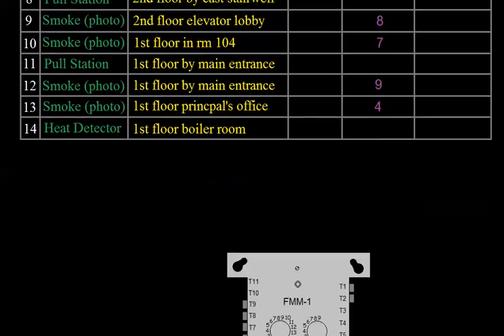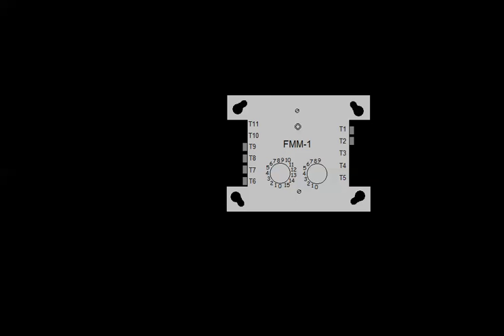The next thing we're going to cover is monitor modules. We've talked about pull stations, smoke detectors, and heat detectors — all addressable devices the panel can communicate with directly. But there are still several devices that aren't addressable: sprinkler devices, conventional heat detectors, conventional duct detectors, and kitchen suppression systems. These are all conventional or contact-closure devices. A monitor module is very simple — its purpose is to act as an interface between an intelligent panel and a conventional device.